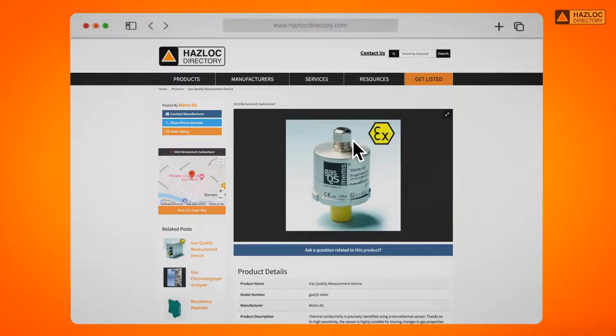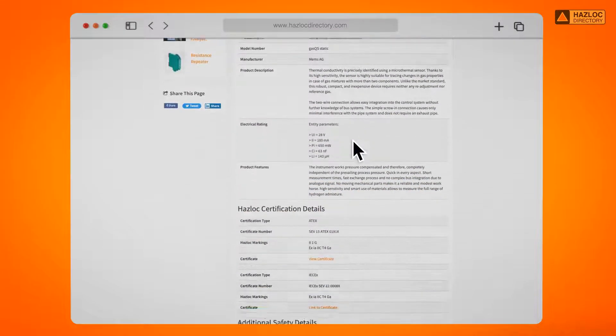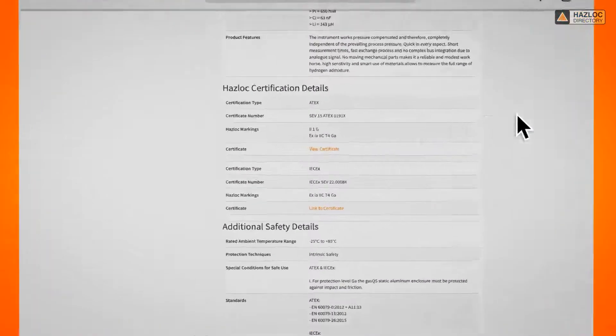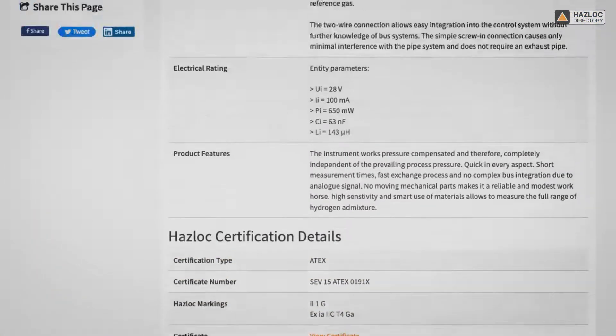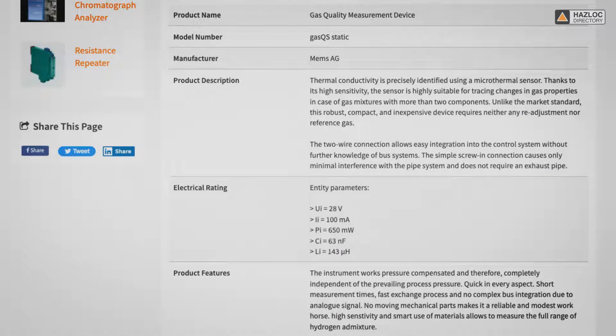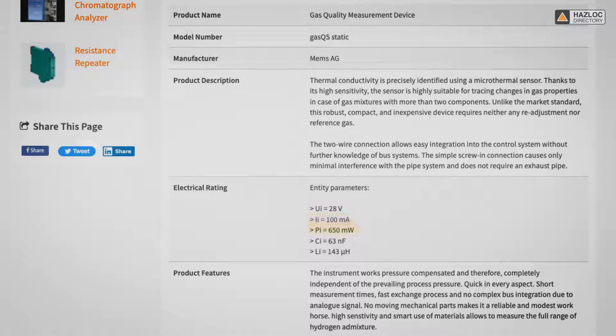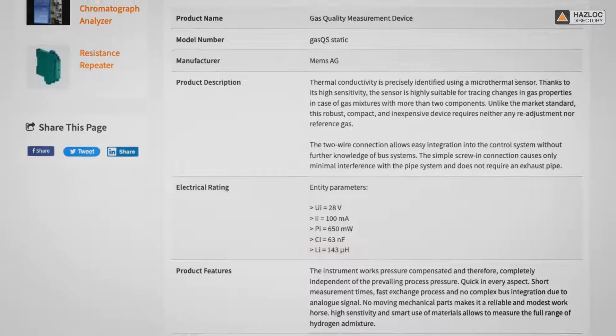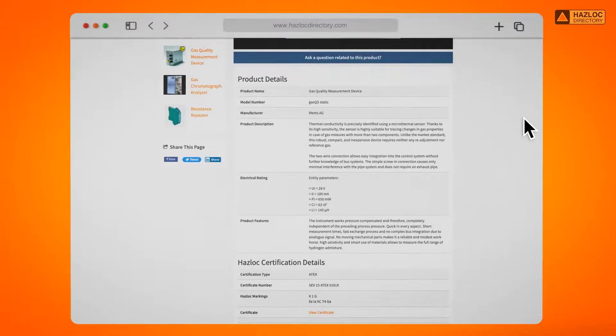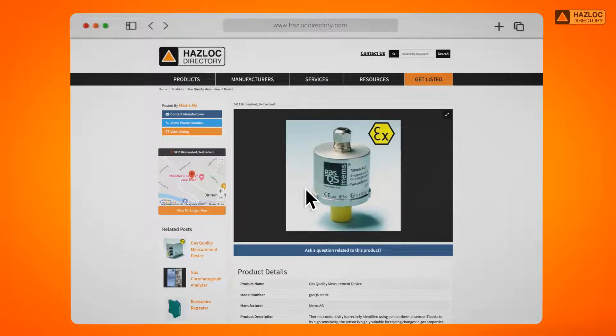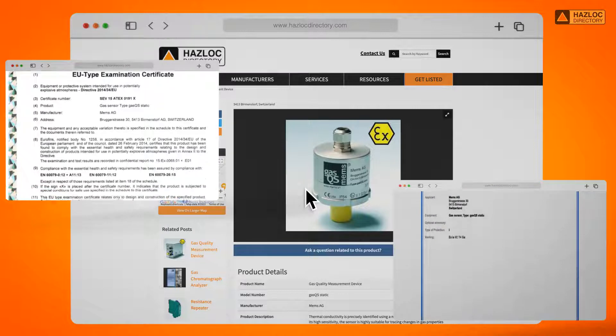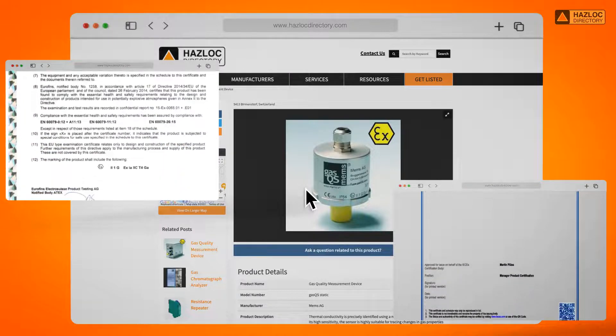This device is listed in the Hazloc directory and is suitable for use in Zone 0 with valid IEC-EX and ATEX certificates. The entity parameters of this IS device are defined as maximum input voltage, 28 volts, maximum input current, 100 milliamps, maximum input power, 650 milliwatts, total internal capacitance, 63 nanofarads, and internal inductance of 143 microhenries. These entity parameters are listed on the devices IEC-EX and ATEX certificates, as well as the Hazloc directory page for this product.